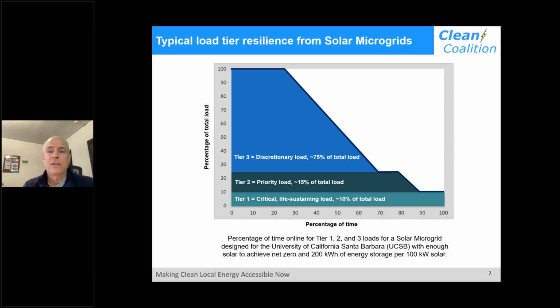The next layer up is the priority tier, tier two, which are priority loads. You keep them on as long as you can without threatening to keep your tier ones on. So tier two loads will be kept on for at least 80% of the time. The remaining loads are discretionary, and even those will be kept on for at least 25% of the time.